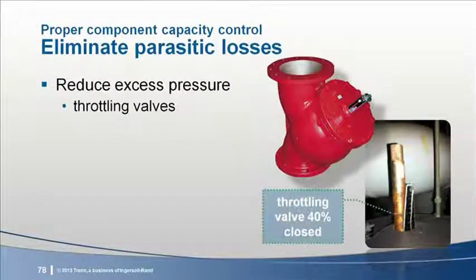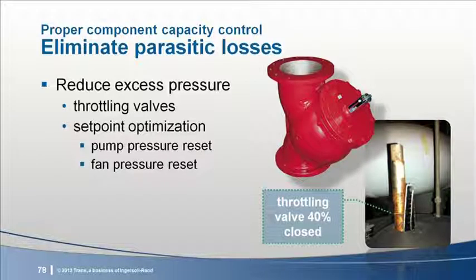We've been in a number of chiller plants with the VFDs on the pumps running at 60 Hertz and triple duty valves cranked 30 to 60% closed. It's a sad waste. Although it's not often thought of as such, another form of parasitic loss is a constant pressure set point on a pump or fan. Using a constant pressure set point requires control valves to consume excess part load system pressure that the pump expended significant energy to create. Using a set point optimization method such as critical valve optimization considerably reduces this form of parasitic loss.